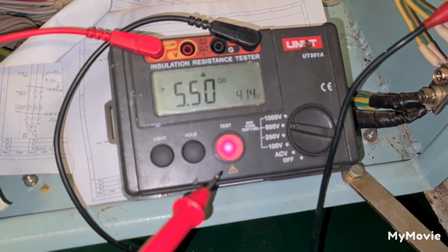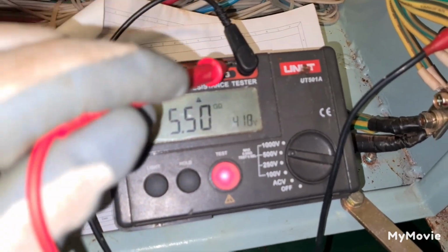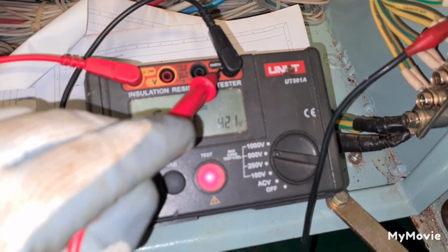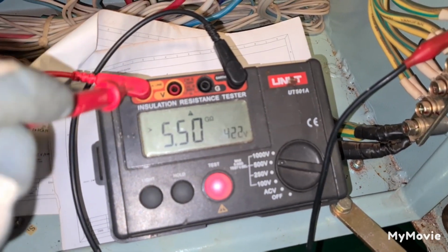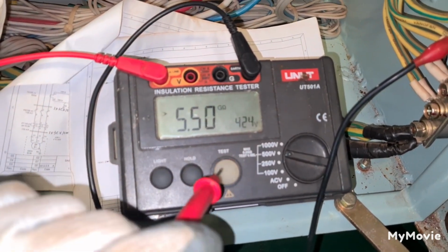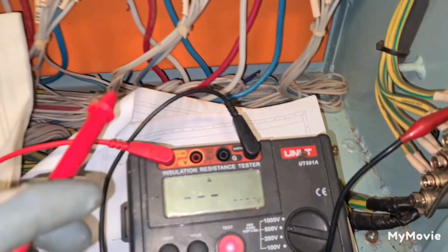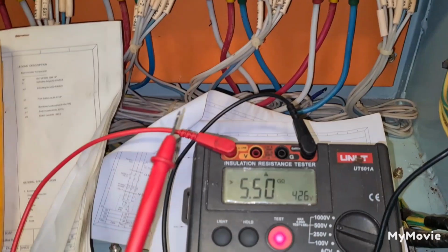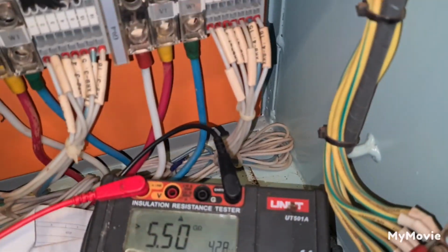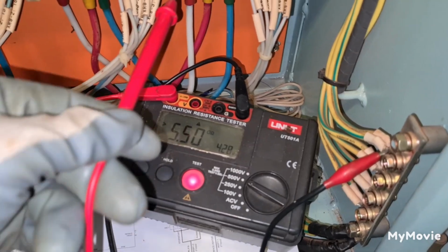For you to do a megger test, you must put this black cable on earth, okay? And then you must put the red on the line. So we can press this one, and we can individually connect it on the cable going to the motor. So from here, I'm going to test now line 1 of my supply fan motor on cargo port number 1.